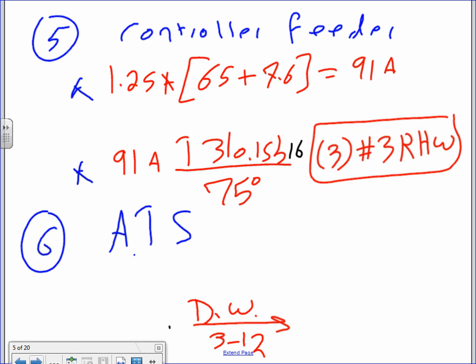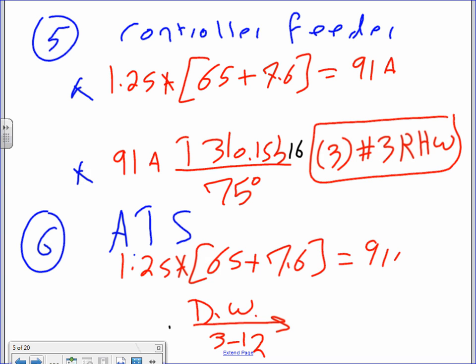ATS. To size the ATS, that's number 6, the same calculation we do. We use 1.25 times the same calculation that we did above. 65 plus 7.6. Add them up, it gets you 91 amps. And then you take your 91 amps to Table 240.6, that will get you 100 amp. 100 amp circuit breaker. Auto transfer switch.